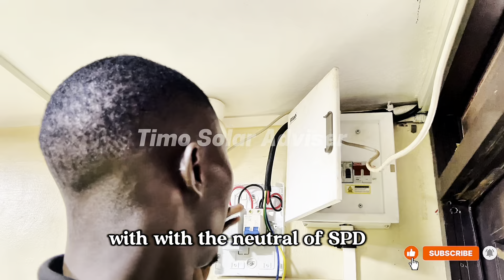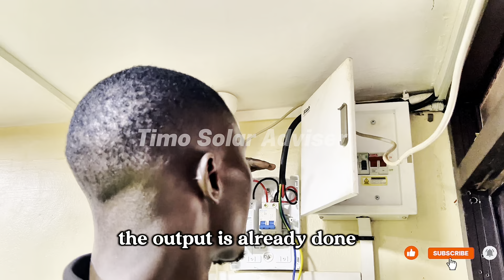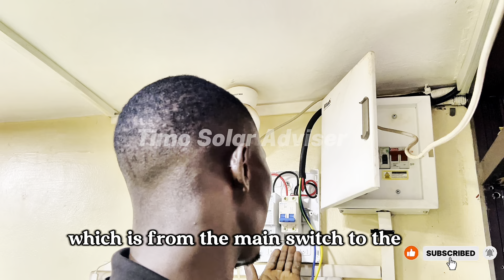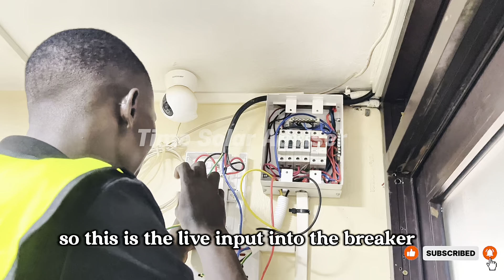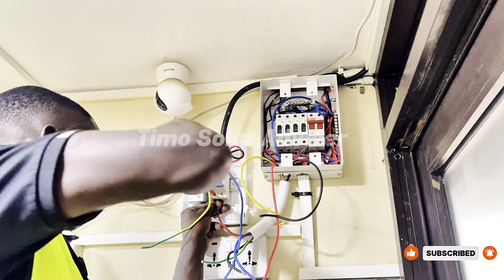The output is already done, so we are going to work with the input, which is from the main switch to the AC breaker. Still, we are going to also bond the earthing from the main switch. So this is the live input into the breaker. This is the positive side out. This is the live side. Still, the input is not yet connected to the MCCB breaker because we are still dealing with this side. So we still have to feed the neutral input at the neutral side of the breaker.